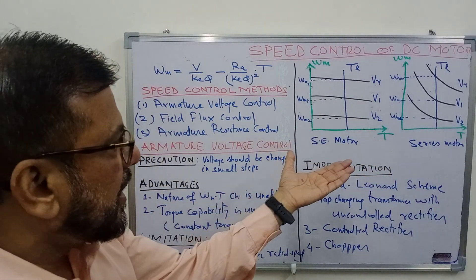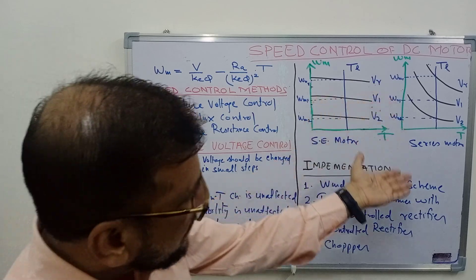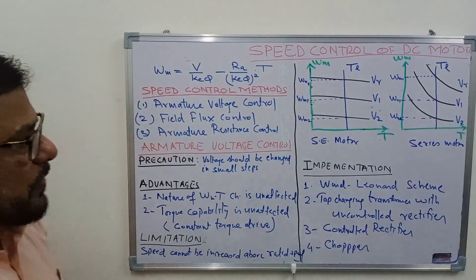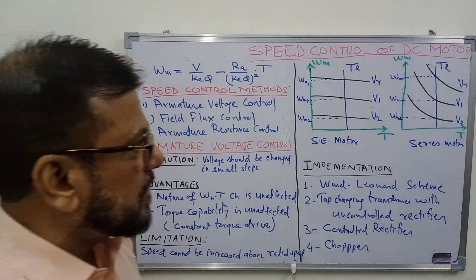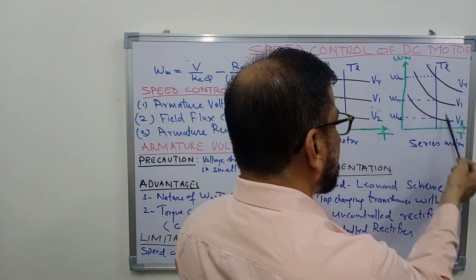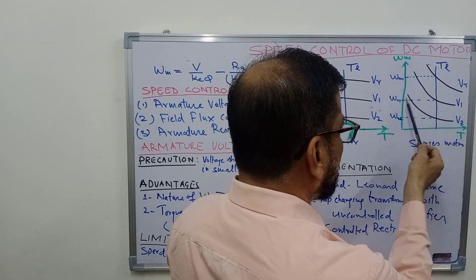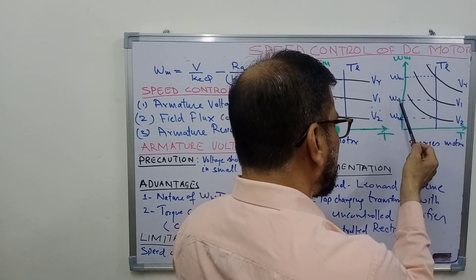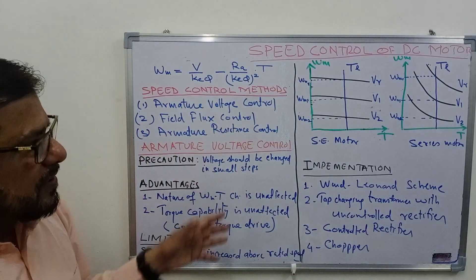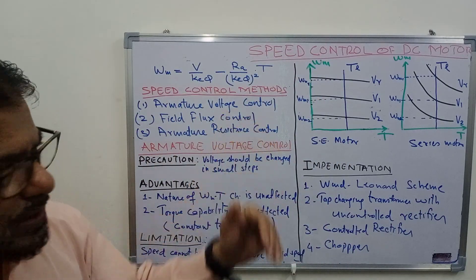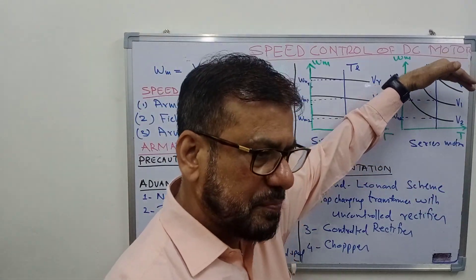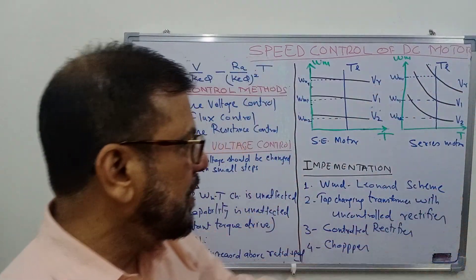This is armature voltage control. Similarly, in the case of the series motor, if you vary the voltage across the armature, the characteristic shifts downward and the speed changes from ωmR to ωm1 to ωm2. In this way you can control the speed over the whole range from rated speed down to a very low speed.